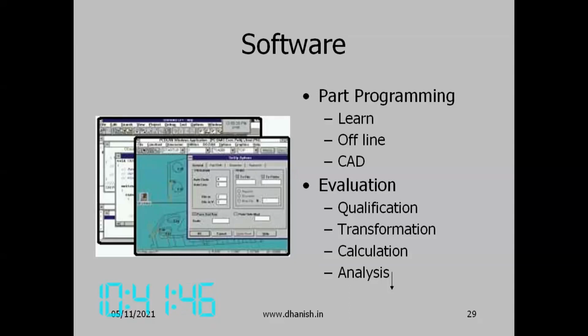We have a standard sphere which is measured using the stylus, and then that data can be used to determine the position of the center of the stylus and the diameter of the stylus, so that we can compensate for the stylus diameter at any position in the machine body. Then the second function is transformation. Recall that one of the major advantages of CMM is that we don't have to align the workpiece with the CMM axis. We just keep the workpiece in an approximate position, which is good enough. Then we probe certain points on the workpiece surface and align the workpiece coordinate system. The measurements actually take place in the machine coordinate system, but that is converted into the workpiece coordinate system and so on.